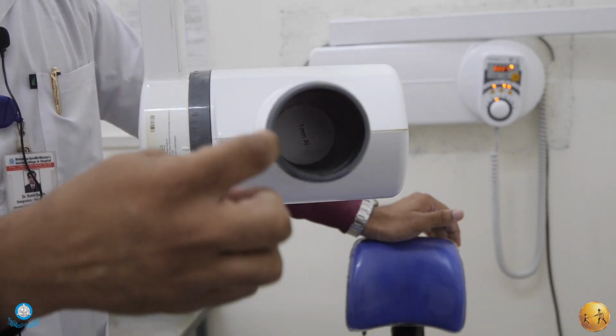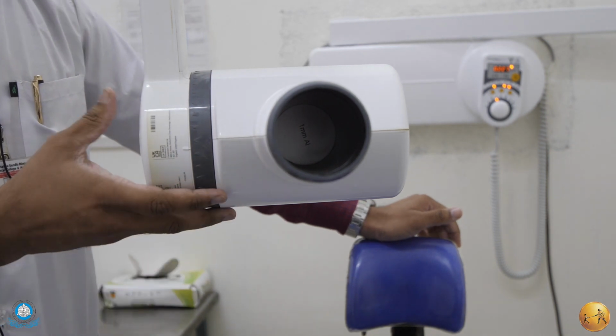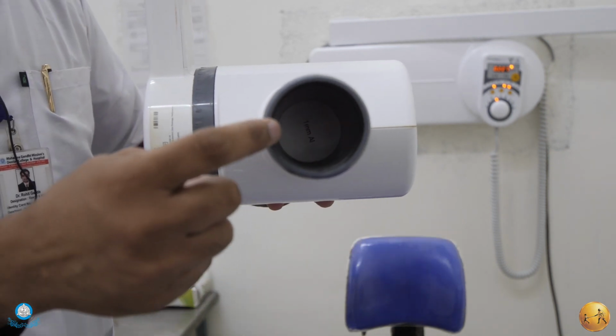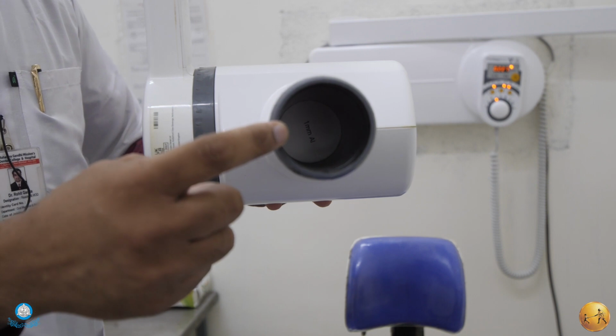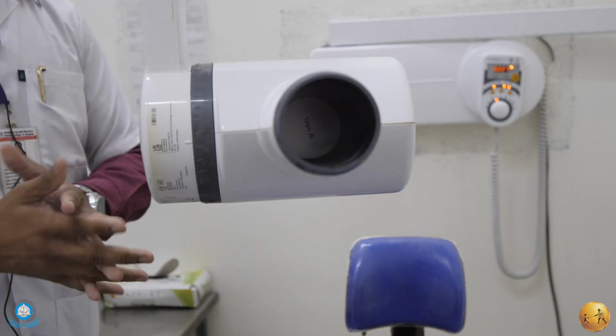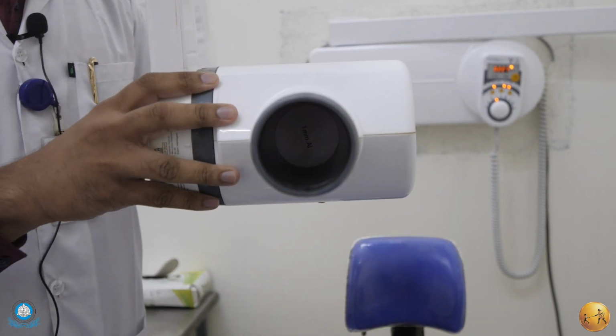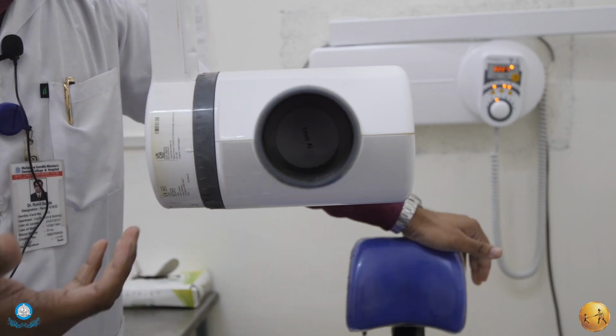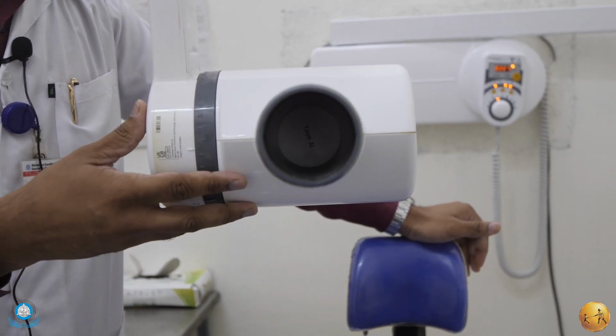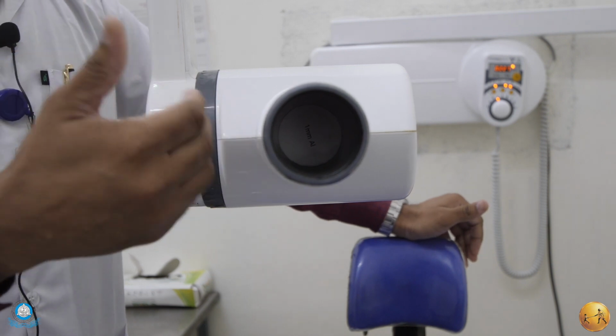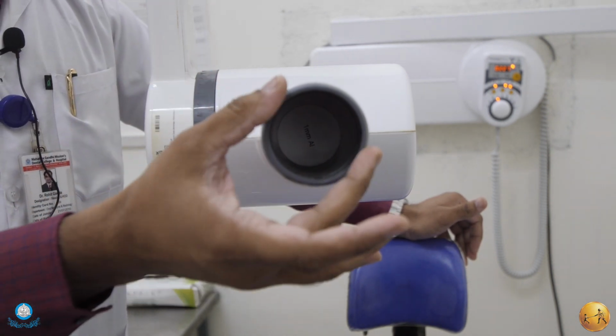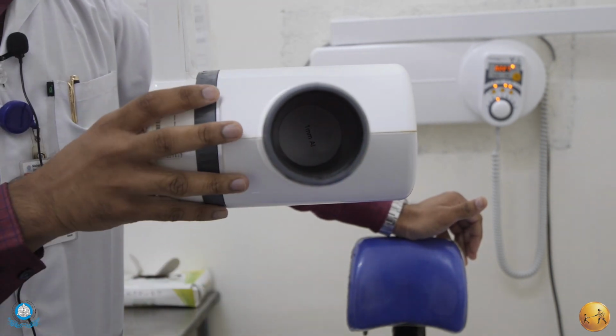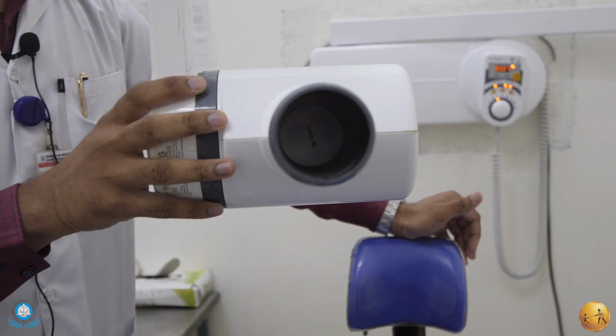Next is filter. Filter is in form of aluminum disc as shown in this. Now function of filter is to absorb low energy X-ray photons which are not useful for image formation. After that, X-rays come out through this position indicating device for radiographic exposure.